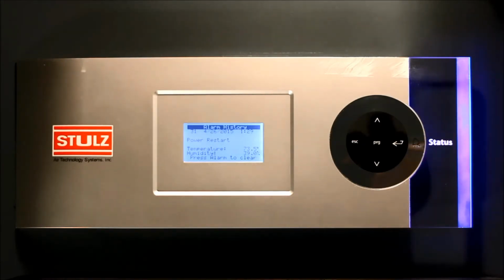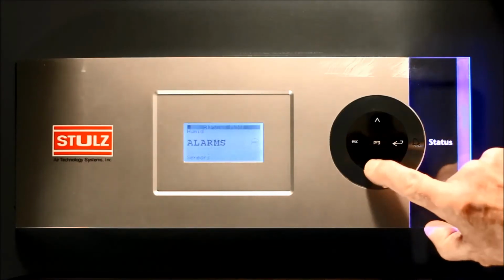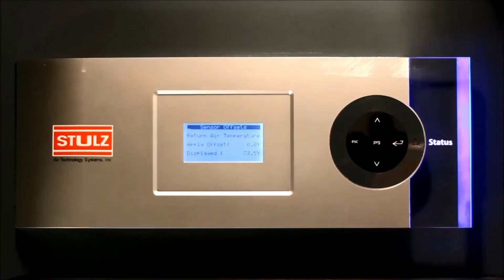In the Sensors submenu, you may view the current sensor reading and apply an offset reading to your sensors for calibration purposes. Please use a calibrated temperature humidity meter when performing this function.